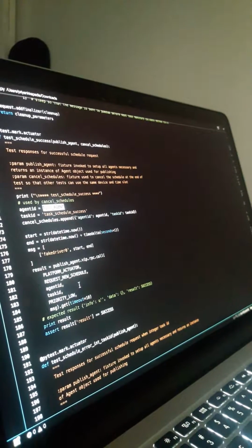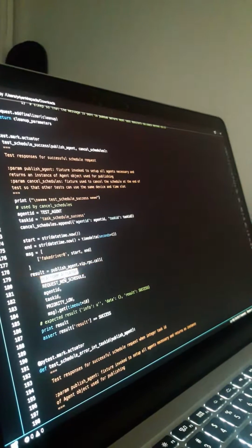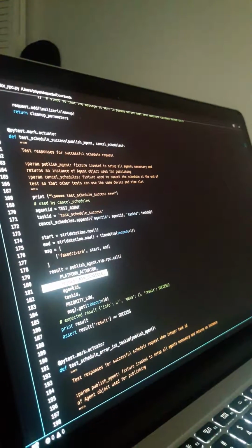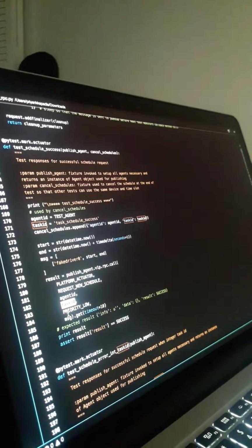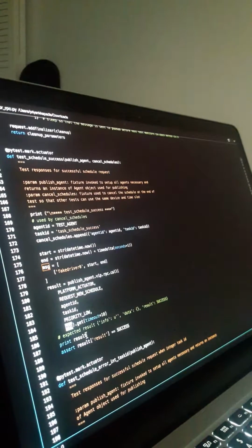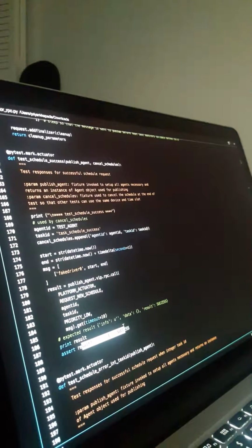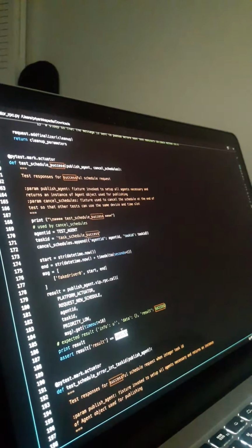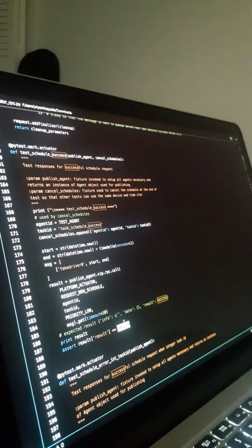Yeah. So I'm just saying that okay, this is my agent ID. This is the example, right? Yes. Yeah, okay. So to the actuator agent, request new schedule for this agent ID for me, and set that priority to low, and this is my start time and end time for this agent. So mostly the test here was to see whether it succeeds or not, and that's why the result returned by that is success here. So the RPC call is a way to schedule your task ahead of time.